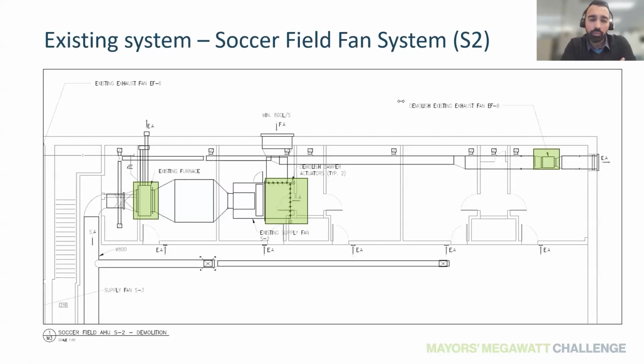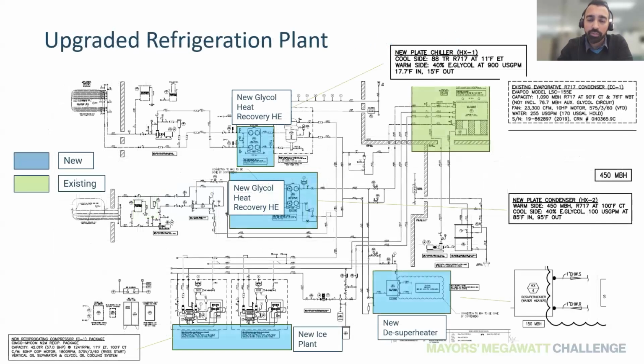As you said, David, the philosophy will always be to look at our assets coming to end of life and come up with a plan that decarbonizes the existing status for us. We get to reduce GHG emissions, reduce energy consumption, and at the same time renew the equipment that is truly end of life. It doesn't mean a complete overhaul of everything we have in place. In this schematic, which correlates to the next one, we had an existing gas-fired furnace and an existing mixed air damper system.